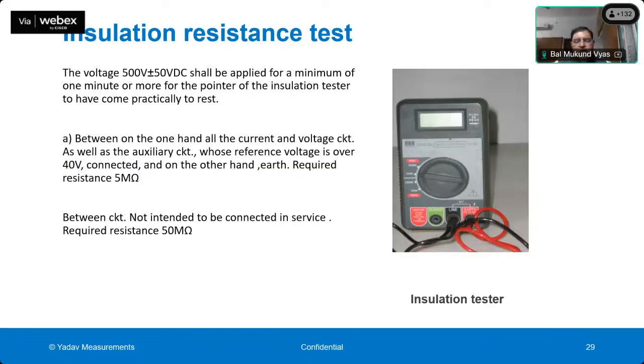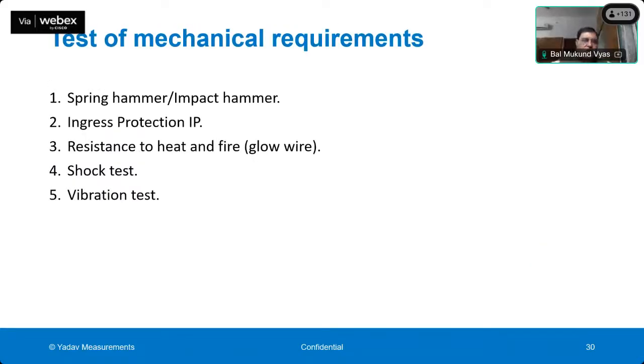Another test is for insulation resistance measurement, which is similar to the AC high voltage test, but the test is done at 500 volt and the insulation resistance is tested, and there are various limits specified. That is between, on one hand, all current and voltage circuits as well as auxiliary circuits connected together, and on the other side, earth. The limit is 5 mega ohm. And between circuits which are not to be connected together, the limit is 50 mega ohm. This is applicable, for example, for a CT operated meter, where there has to be insulation between the voltage circuit and the current circuit. So these were all insulation requirements.